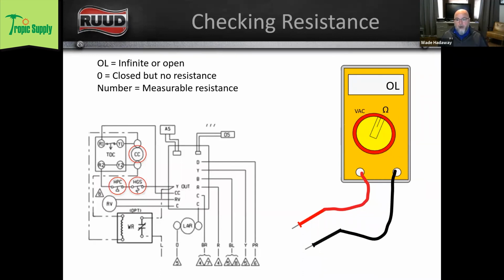You can see right now we've got our meter. The leads are not touching. There is no complete circuit between our red lead and our black lead. This circuit is open, so your meter is going to read OL or infinite. Depending on what type of meter you have, it might show an infinity symbol, like a sideways 8, but typically it's going to show OL. It might show 0, which means that the switch is closed, but there is no measurable resistance across that switch, which is what we want to see.